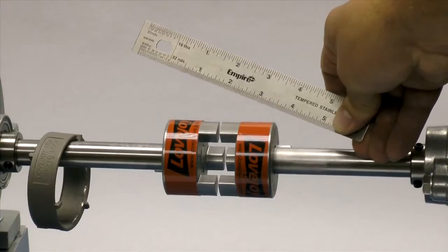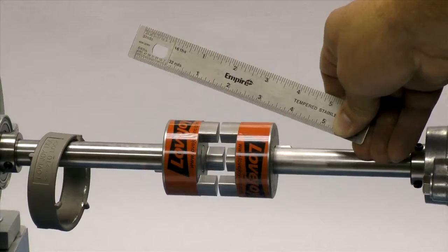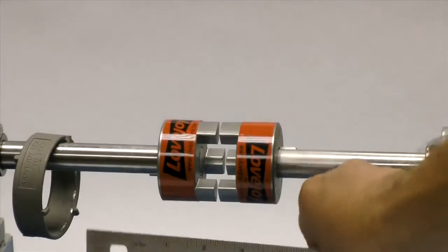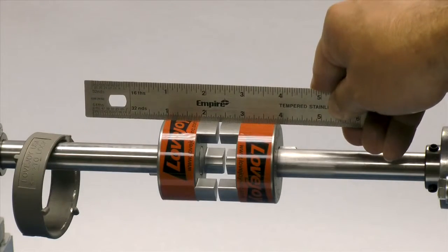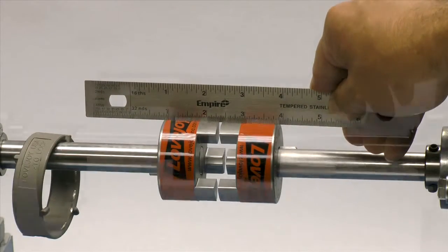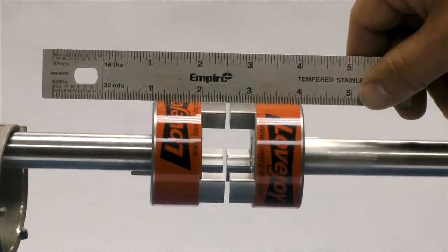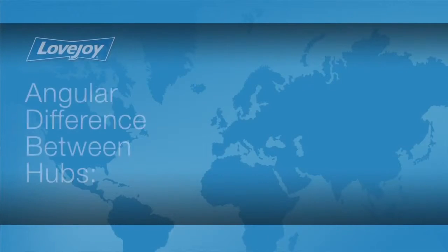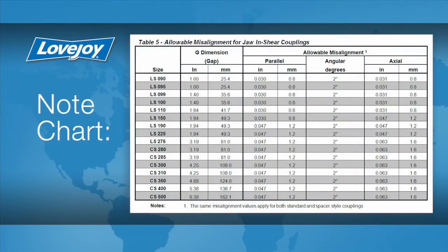Lay a straight edge across the hubs to check the basic alignment. If all sides of the coupling are accessible, check the hubs at four locations — three o'clock, six o'clock, nine o'clock, and twelve o'clock — without rotating the shafts. The offset between the two hubs must be less than 1/64th of an inch to prevent damage to the coupling. The angular difference between the two hubs should be less than 2 degrees for the jaw in-shear style urethane spiders. If the alignment exceeds the allowable amount, realign the equipment to correct this condition.